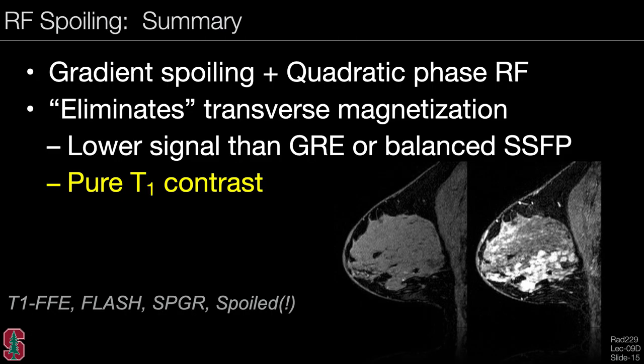To summarize RF spoiling: it uses gradient spoiling with an additional quadratic phase RF. The goal is to eliminate the transverse magnetization. This gives a lower signal than GRE or balanced SSFP since we are eliminating signal, but it gives a pure T1 contrast. The terms FLASH, SPGR, and T1FFE describe this contrast.